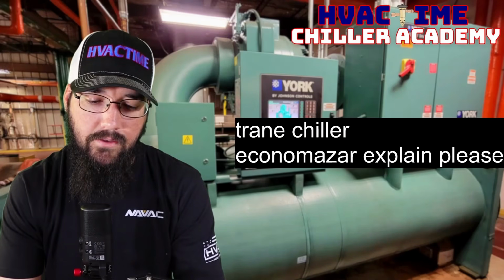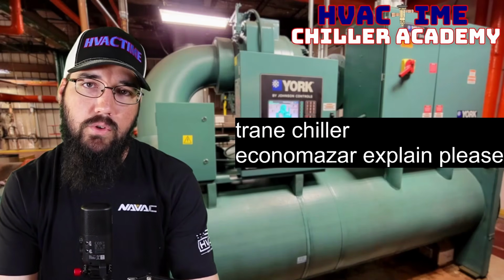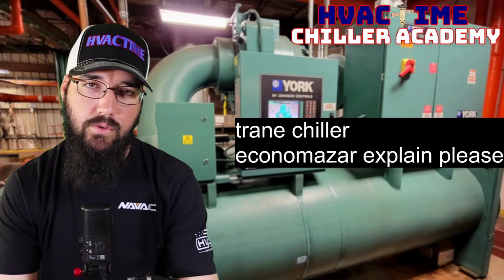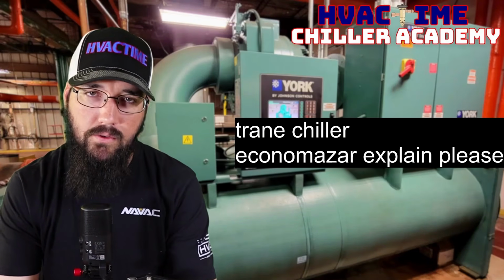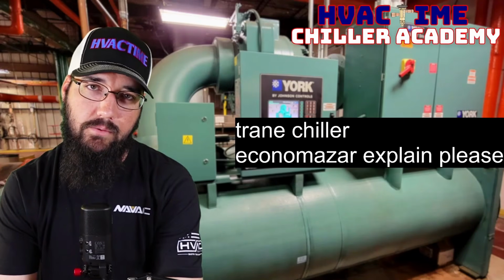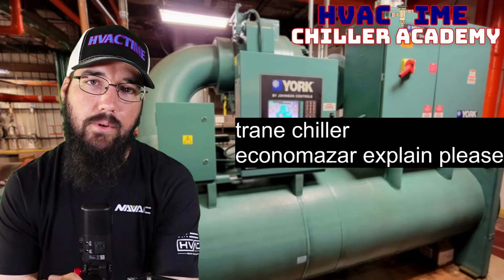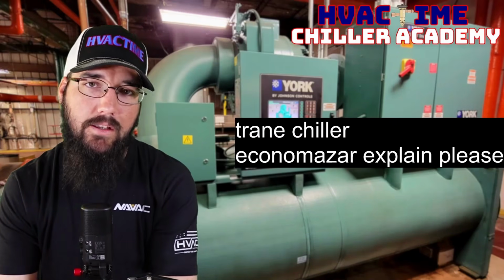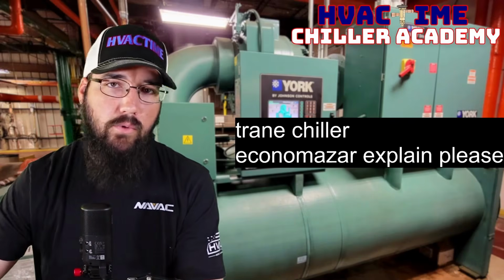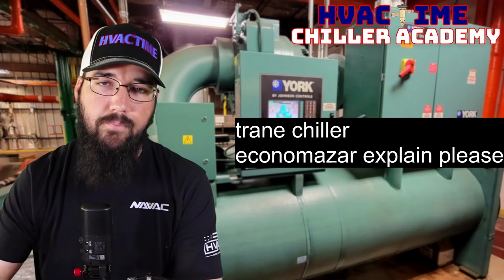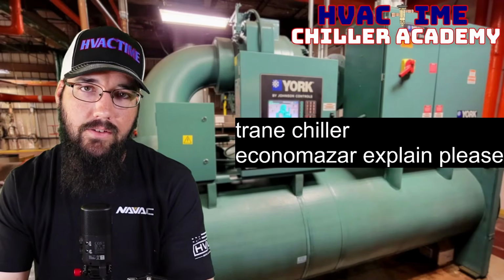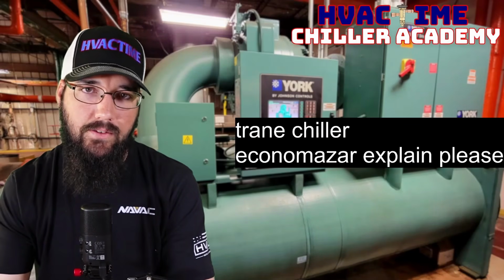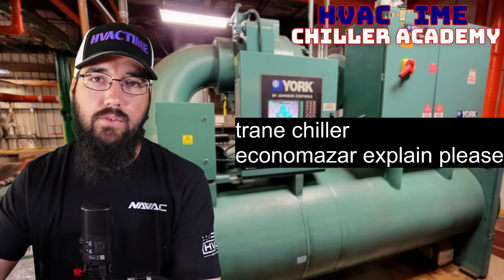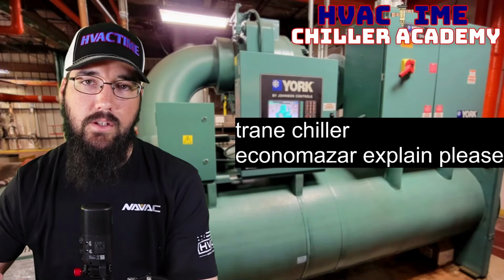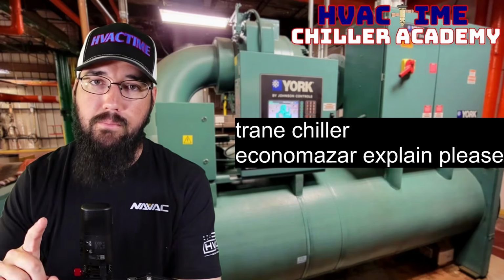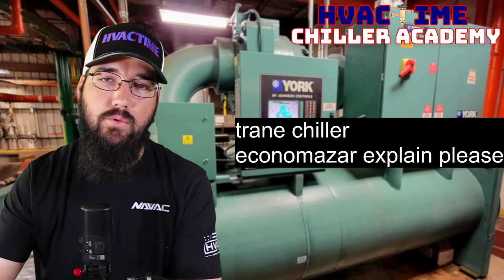And we can do that by making better use of our refrigerant to not only reduce some of the load on the compressor, but also we can improve our effectiveness of the refrigerant by reducing what we call enthalpy. Enthalpy is the actual heat content of our refrigerant. Without getting crazy into enthalpy as a term, the point is it's just showing us the amount of heat that something contains. The economizer allows us to lower the enthalpy, which allows the refrigerant to be more effective. But it also allows us to reduce some load on the compressor.